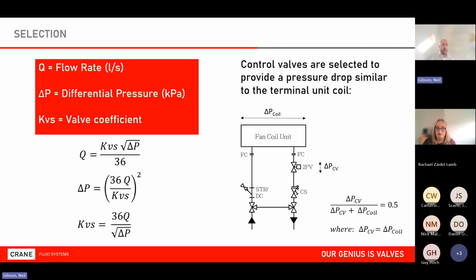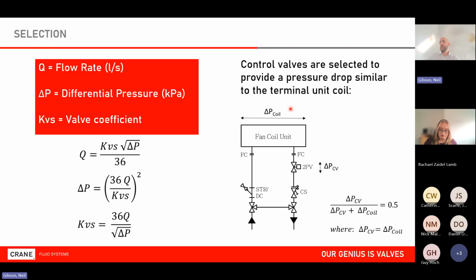The issue is that with a control valve, if we're using it to serve a terminal device, it needs to be sized. Every single one needs to be sized. What I just want to briefly show you as an example, if we look at this, let me do the pointer, that will help. I've got the differential pressure across my coil, and I've got my 2-port valve here. The aim for the 2-port valve is to have the same pressure drop as the coil at design load. We can represent that in this simple calculation. The dP over the control valve, divided by the control valve plus the coil, equals 0.5. That's the target. That's what we want.